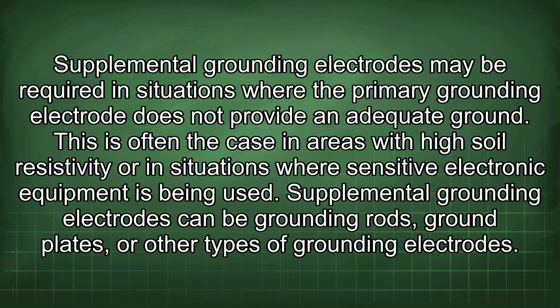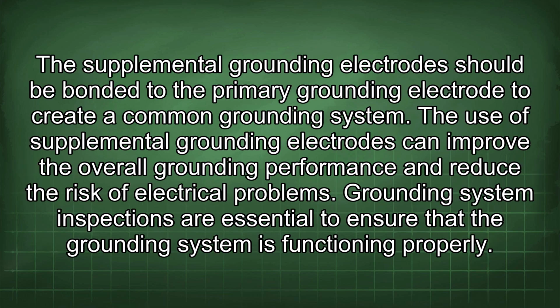This is often the case in areas with high soil resistivity or in situations where sensitive electronic equipment is being used. Supplemental grounding electrodes can be grounding rods, ground plates, or other types of grounding electrodes. The supplemental grounding electrode should be bonded to the primary grounding electrode to create a common grounding system. The use of supplemental grounding electrodes can improve the overall grounding performance and reduce the risk of electrical problems.